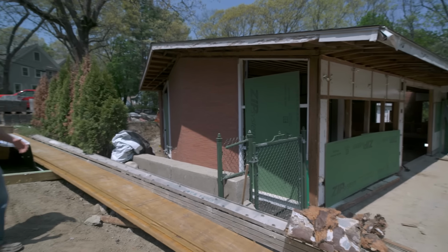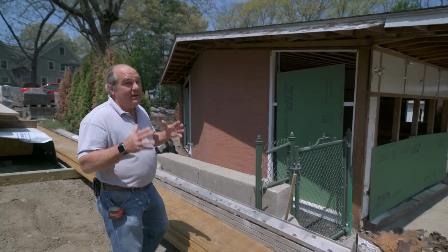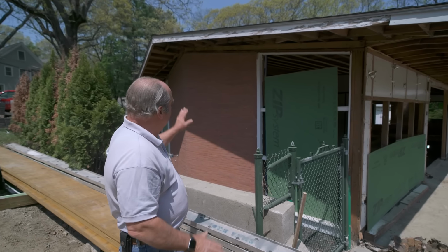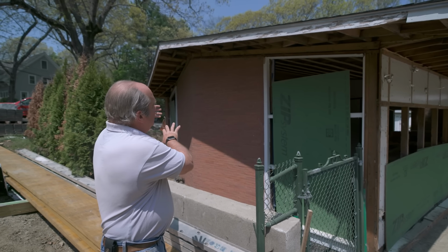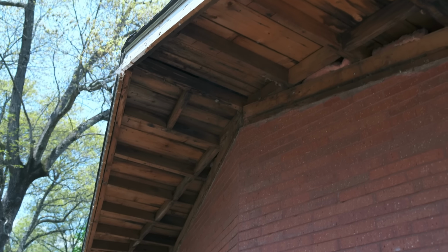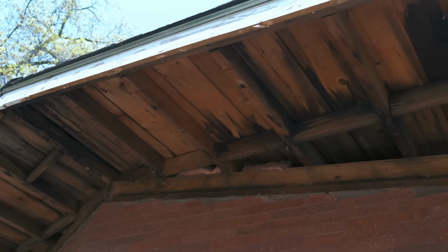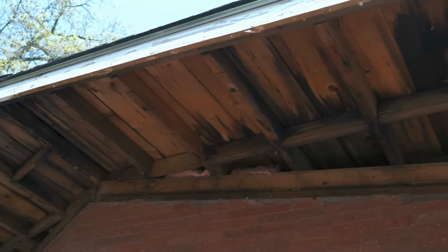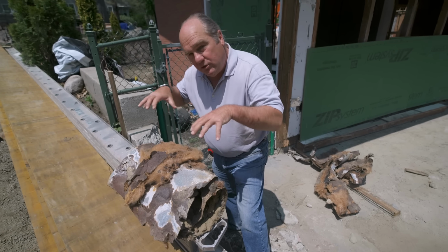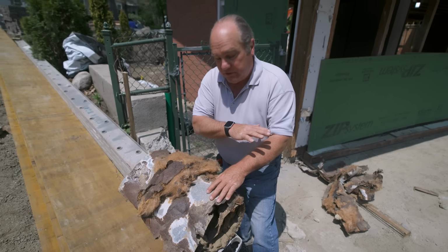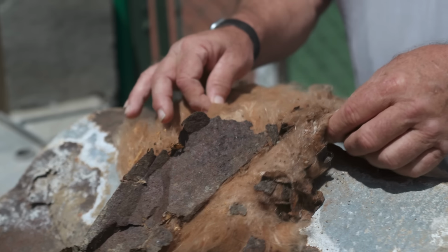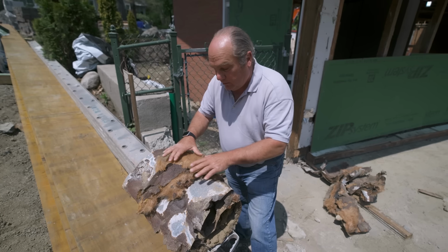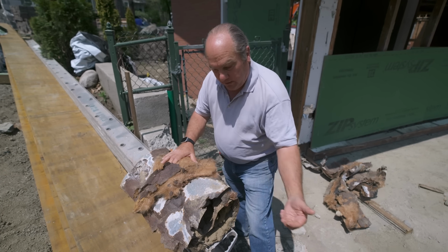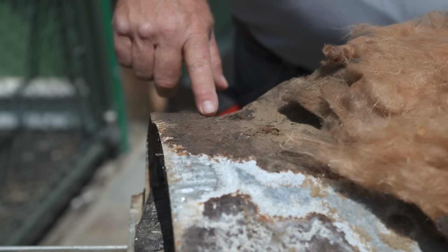When this house was built in 1960, the HVAC contractor had a particular challenge on this end of the building. These are solid brick walls on these two sides, and there's no attic, no place to hide ductwork. So the only choice they had was to run ductwork under the concrete slab. The material of the day was simple metal, and this is all that's left of it. It would have been entombed in the dirt with concrete over the top. The insulation of its day was fiberglass, which could pick up moisture, and once you introduce moisture from the ground and the ductwork, look what it does. It rots away the metal.